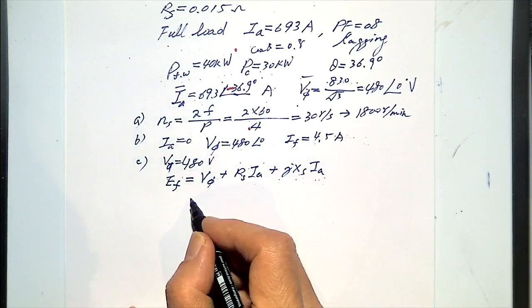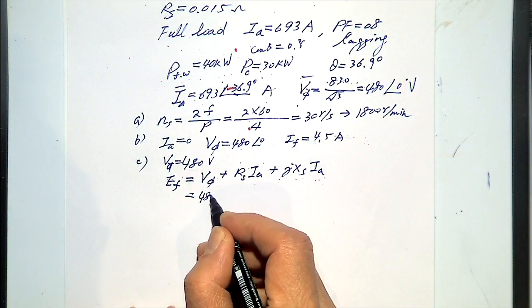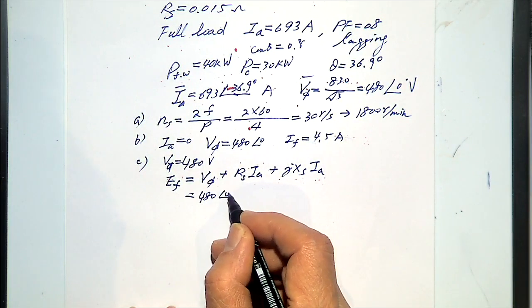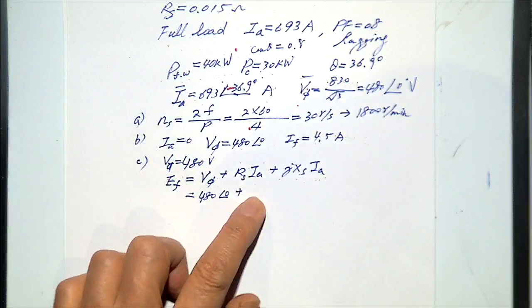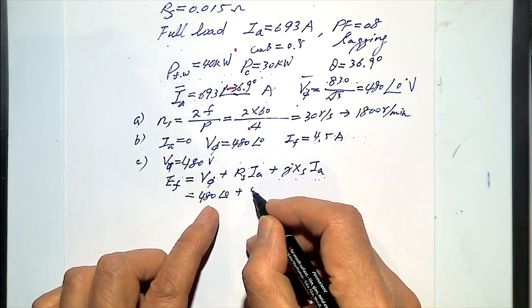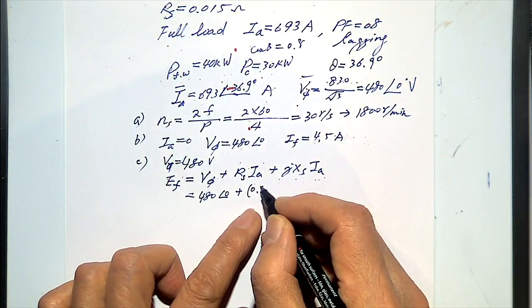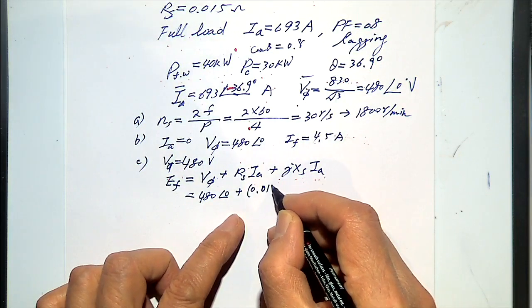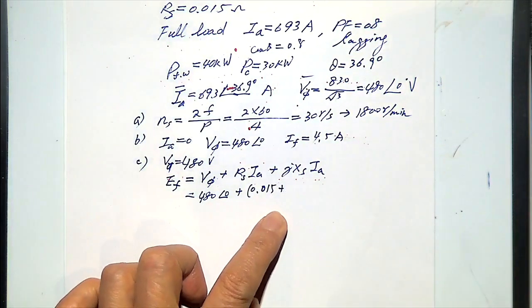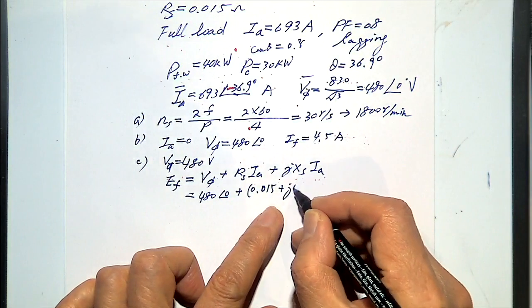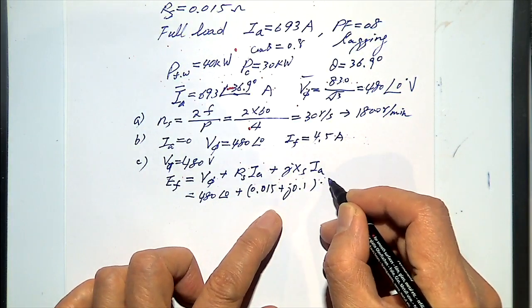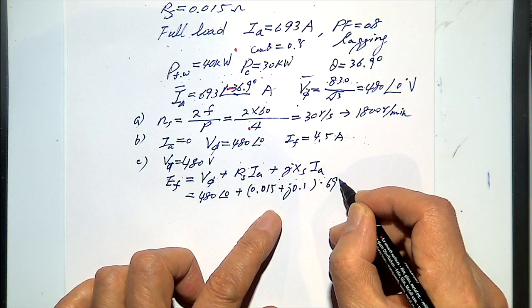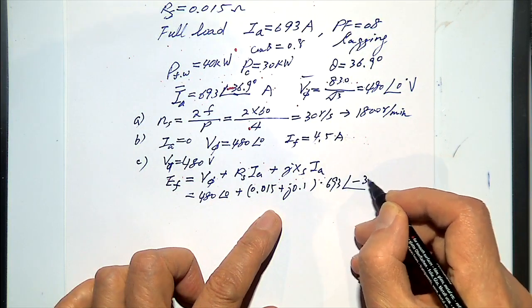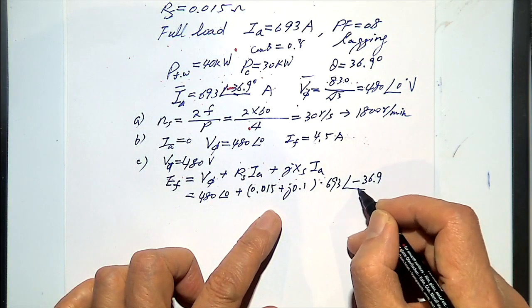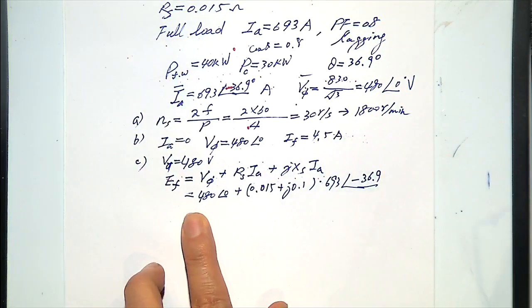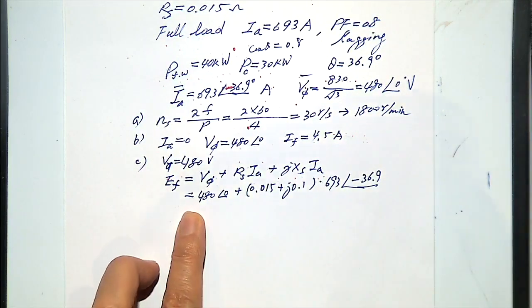So here: 480 at 0 degrees, plus RS which is 0.015 plus J0.1, multiplied by IA which is 693 at minus 36.9 degrees. That's the equation, and from it you calculate.